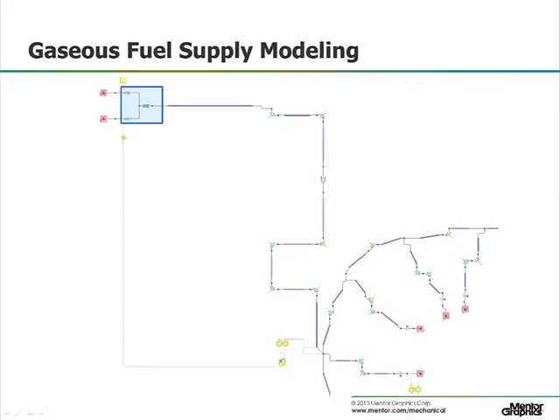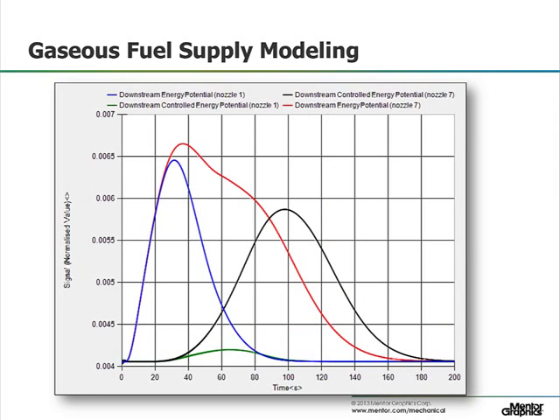Our proposed solution to this problem is to try and move the measurement point for heating value as close to the injectors as possible. This may introduce some oscillation into the control, as there's a large delay time and compressible gas column between the actuated valve and the measurement point, but hopefully the mixture itself is more stable. After switching the heating value measurements to just before the first nozzle and rerunning the analysis, we can compare the previous results with the new results.